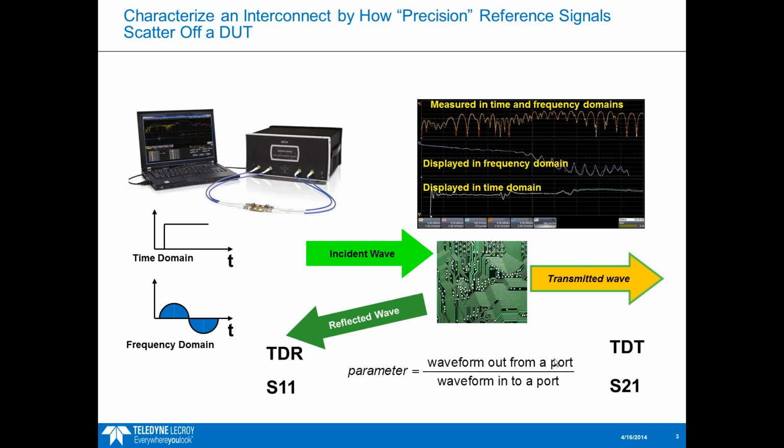In a typical VNA and TDR, you need to hook those up manually to the test port cables and measure each of them. On the Spark, all that is done automatically for you. You just need to press the button and make the measurement. You don't need to hook those up externally. Hopefully this answers it. If not, you can resend your question.